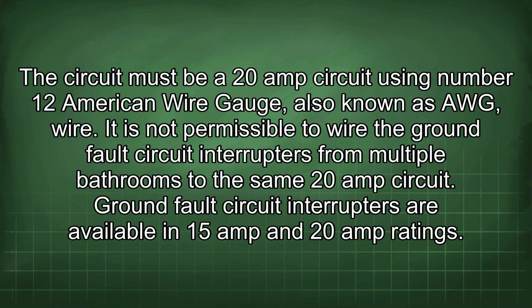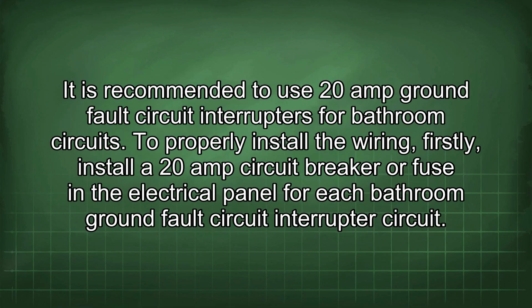It is not permissible to wire the ground fault circuit interrupters from multiple bathrooms to the same 20 amp circuit. Ground fault circuit interrupters are available in 15 amp and 20 amp ratings. It is recommended to use 20 amp ground fault circuit interrupters for bathroom circuits.